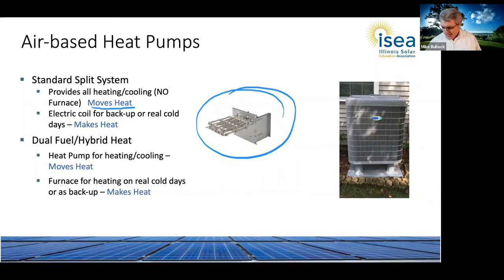That is definitely an option. And then there's the dual fuel approach, or hybrid heat, could be called either one of those things. It's where you have a heat pump for heating and cooling. It moves heat. And then when it's really cold, or if there's some failure, you have a furnace, and that's what I have. That furnace makes heat. So those are the two typical ones for air-based systems for residences that leverage the ductwork already in your house.